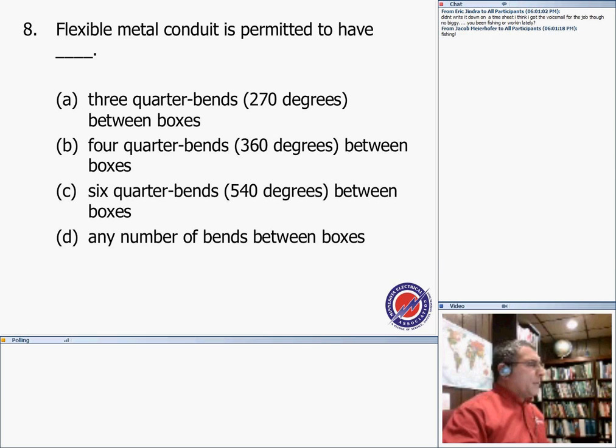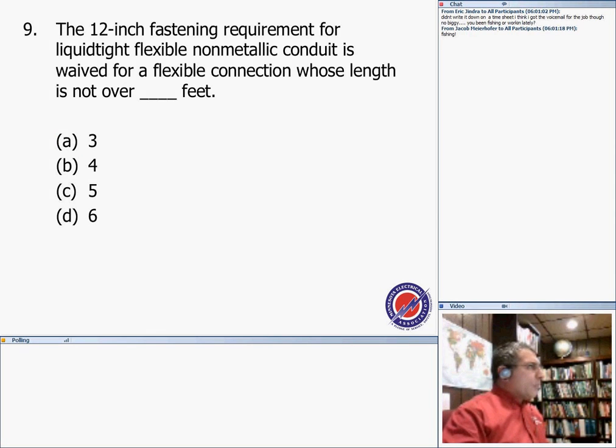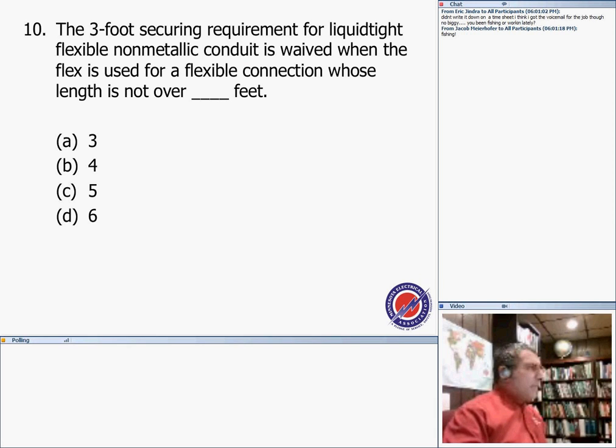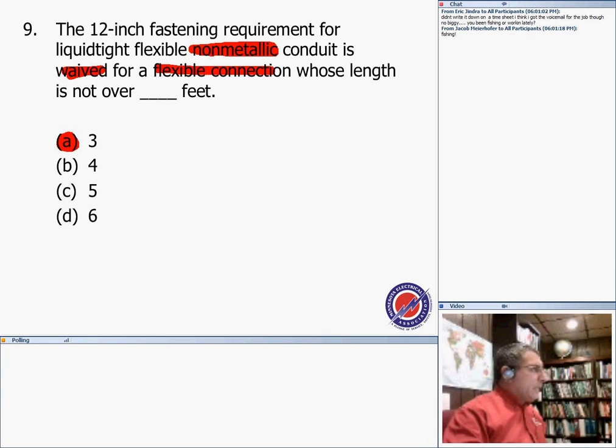Number 8, flexible metallic conduit is permitted to have bends like any other conduit, but you can't bend it more than 360 degrees. No question asked. Number 9, the 12-inch fastening requirement for liquid tight flexible non-metallic conduit is waived for flexibility when the length is not more than 3 feet. And I want to emphasize the word non-metallic. That one, a lot of you guys got it wrong too. I think probably you were not looking at the non-metallic. You were looking at liquid tight metallic conduit maybe.